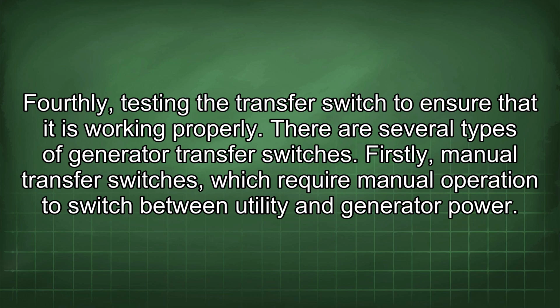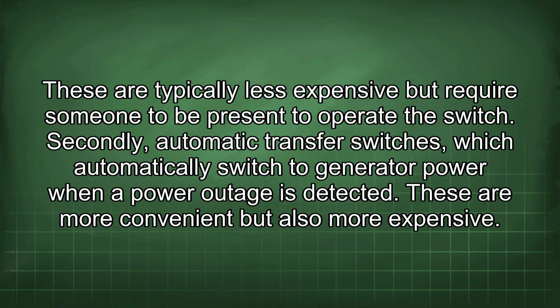There are several types of generator transfer switches. Firstly, manual transfer switches, which require manual operation to switch between utility and generator power. These are typically less expensive, but require someone to be present to operate the switch. Secondly, automatic transfer switches, which automatically switch to generator power when a power outage is detected. These are more convenient but also more expensive.